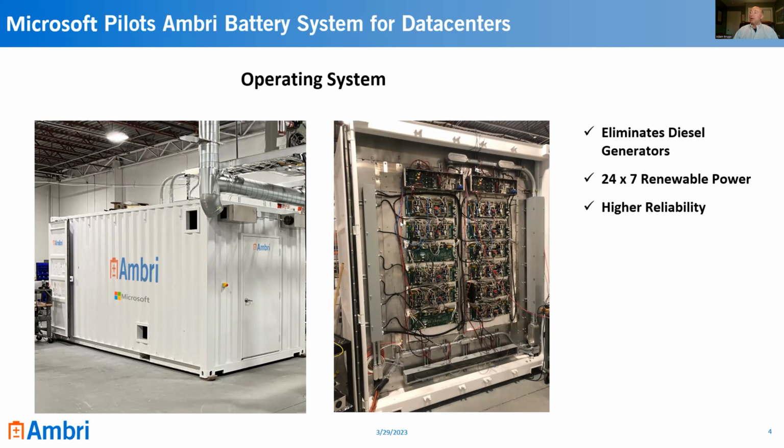essentially the trays or the shelves that have been inserted into this. There are 12 of them, and each of them has electronics. So we measure the voltage of each cell. That cell then is monitored for balancing on a real-time basis. We have a battery management system integrated into this container. So you can see the system can be operated with the doors open or closed. But of course, inside or behind these electronics, the temperature is high, and we're not anticipating that we're going to open that system during the life of the system, and we're not going to service anything inside that system on a preventative basis.